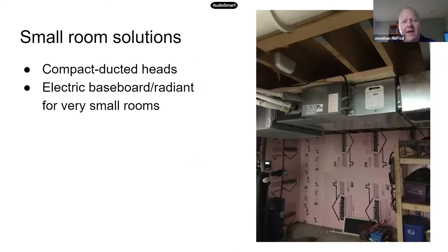One that we really like a lot are these compact ducted heads. So instead of a ductless head in each room, we might have a compact ducted system, which is what you see here. It's essentially a little air handler that's hooked up to a very compact duct system and provides heating or cooling to one part of the house. In this case, this was a cute little three-bedroom ranch, and we put a high wall head, like you saw in the previous picture, in the great room, which served the great room, dining room, kitchen area. And then for the bedroom wing, we put in this compact ducted air handler. It had three short duct runs that went to each of the bedrooms.